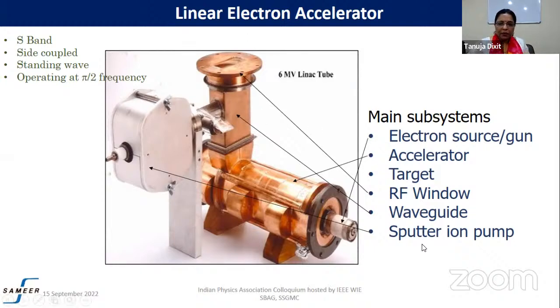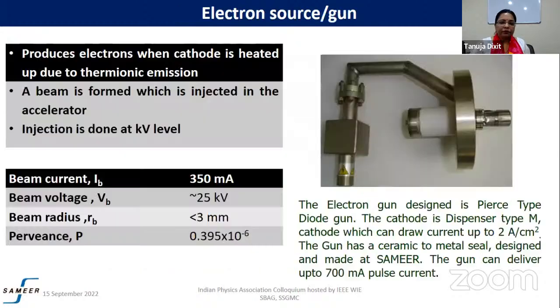These are the main subsystems of this LINAC: the electron source or gun, which produces electrons; the accelerator, which is this copper structure, a cylindrical waveguide; the target, to produce X-rays; the RF window, which separates the vacuum part from the pressurized SF6 part where megawatt power flows through the waveguides; and also the sputter ion pump, to take care of residual outgassing during operation.